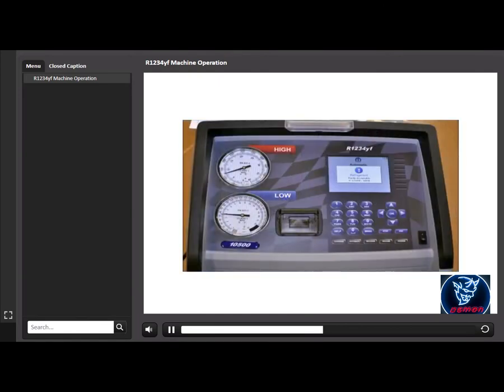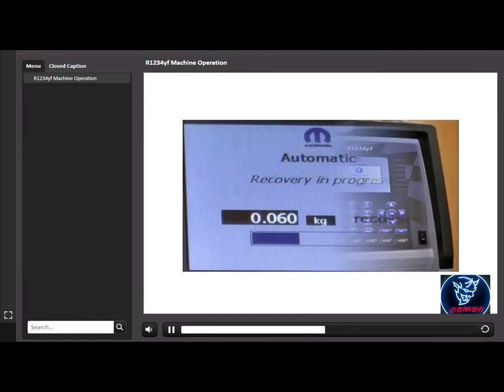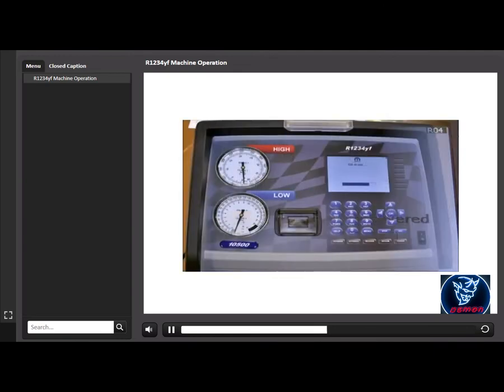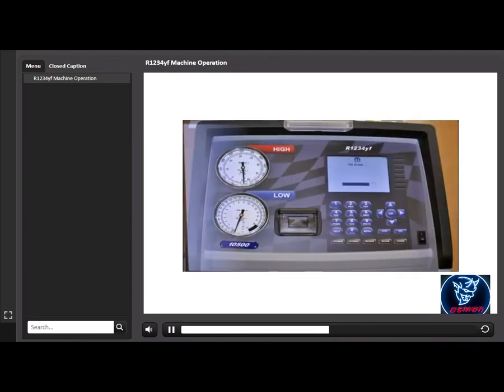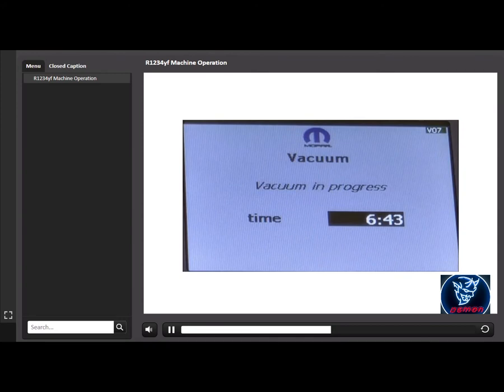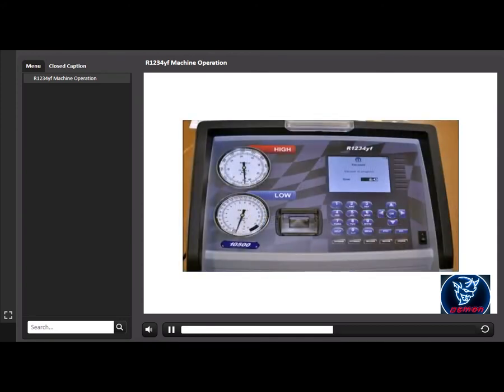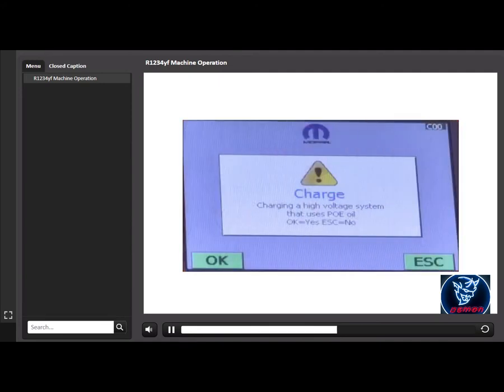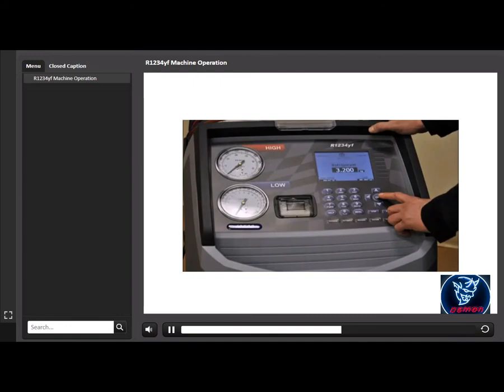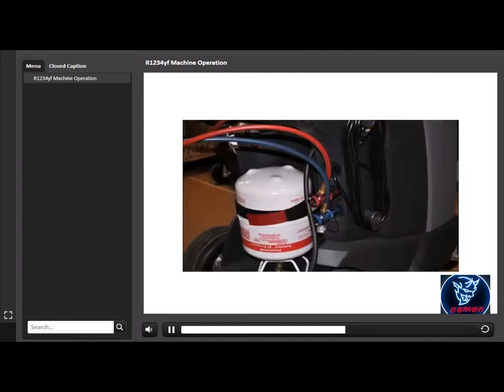If the purity reading is acceptable, the machine performs a recovery and the system oil is drained at the end of the recovery sequence. If the vacuum time was programmed, the machine will perform the vacuum sequence at this time. If a charge was selected, the machine displays charging a high voltage system that uses POE oil. If OK is selected for a high voltage system, the machine prompts for a hose flush procedure. Connect high side and low side service hoses to storage ports on the machine and open the coupler valves.